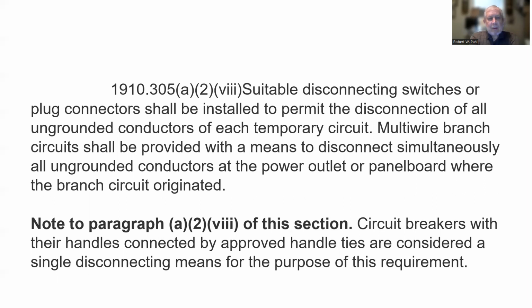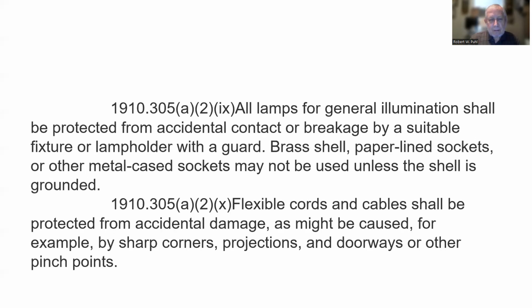Multi-wire branch circuits shall be provided with the means to disconnect simultaneously all ungrounded conductors at the power outlet or panel board where the branch circuit originated. Note, circuit breakers with their handles connected by approved handle ties are considered a single disconnecting means for the purpose of this requirement. We've all seen that. You've seen a panel board that has like three circuit breakers all tied together. So they're considering that as one. And that makes a lot of sense too. That's why they're tied together.